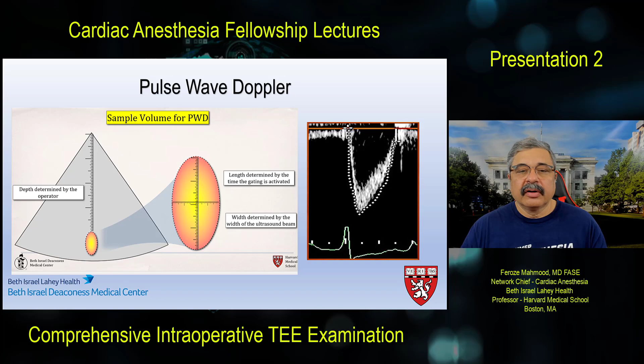So depth is achieved by electronic gating, which means, for example, hypothetically speaking, if we were to know the speed or Doppler shift or the direction of flow 1540 meters from the transducer, then we would send out the pulses, but we will only analyze the pulses that take 2 seconds to come back, because the speed of sound is 1540 meters per second. By putting the sample volume at 1540 meters, we have time gated our pulse wave Doppler by saying that whereas reflection will be happening all through the course of this transmission and reflection, all other reflections will be ignored other than the ones that take 2 seconds to come back, and that's called time gating.